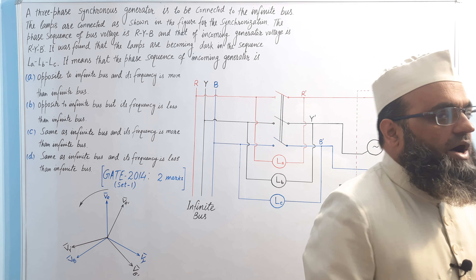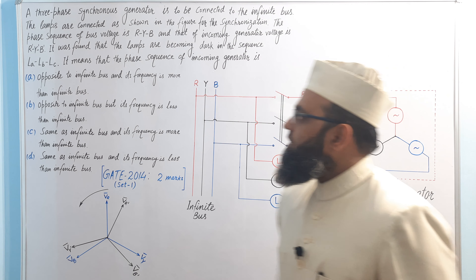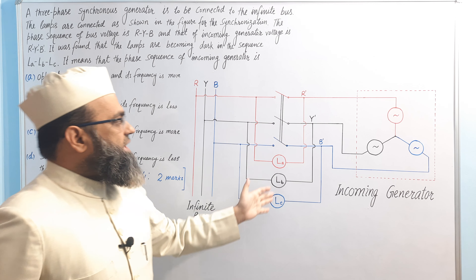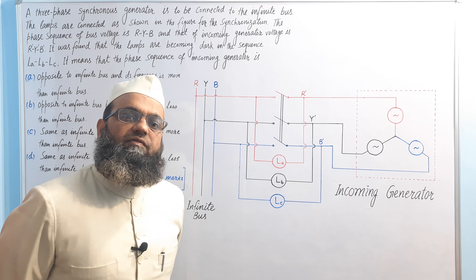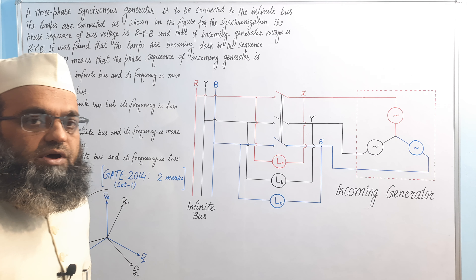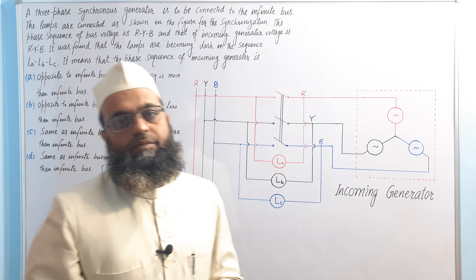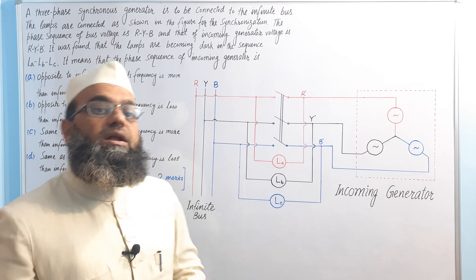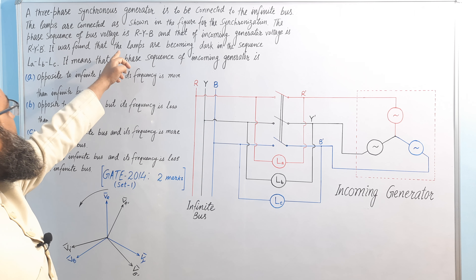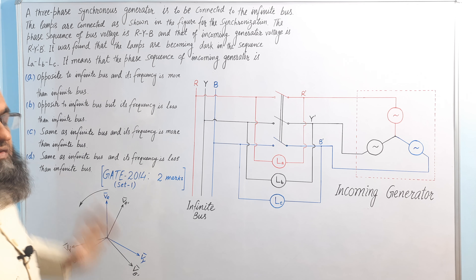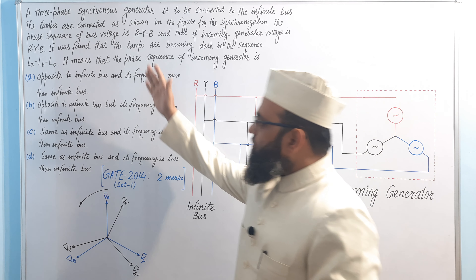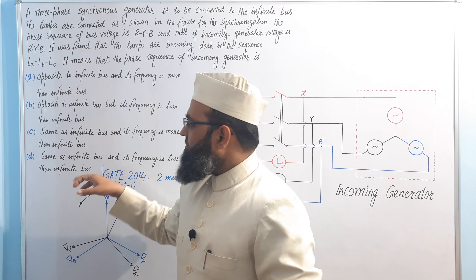For answering such questions, remember the basic concept. The three lamps are directly connected to respective phases of the alternator and infinite bus — no cross connection. This means the two phase sequences will be the same only if all lamps become dark together. But in this problem the lamps become dark in sequence, meaning the phase sequences are not equal. So the two 'same' options are omitted.